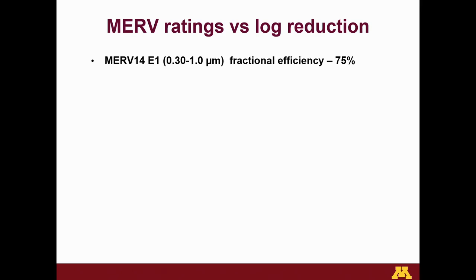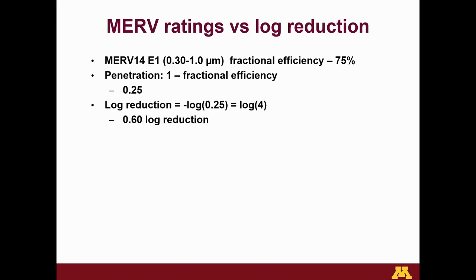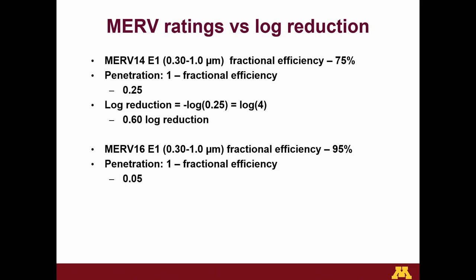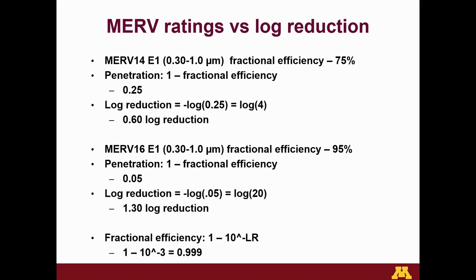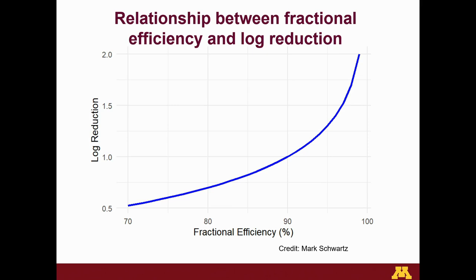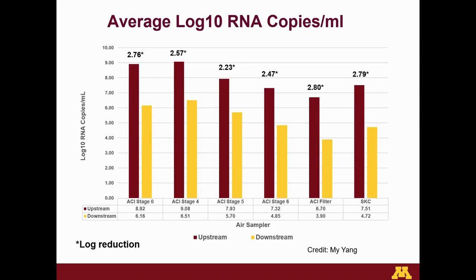So I put this together. A MERV 14 filter, E1, that's a small particle, fractional efficiency of 0.75, so the penetration is 0.25. The log reduction is the negative log of that. You convert it, and you're dealing with a 0.6 log reduction. Remember that number? MERV 16, the same math, we're looking at about a 1.3 log reduction. And a 3 log reduction, I'm working backwards now, is 99.9 fractional efficiency, or penetration of 0.001. Important numbers to remember as we compare filters to our outcome on this study. I threw this together. It's just a nice little handy curve. You can look at that and say, well, what's my log reduction? How would that correspond to a fractional efficiency as a MERV rating?